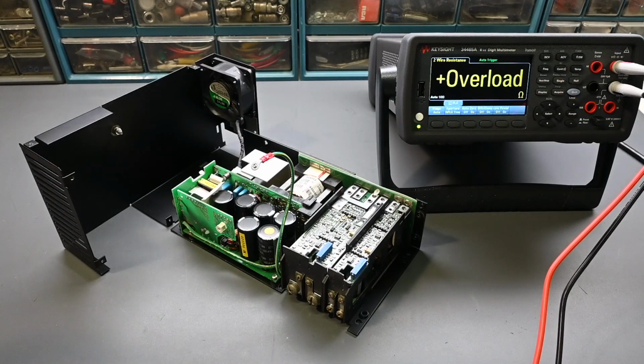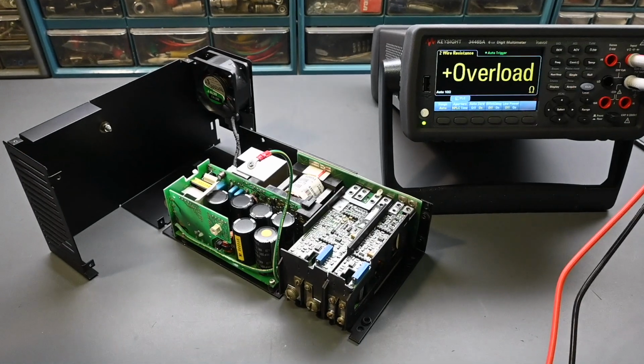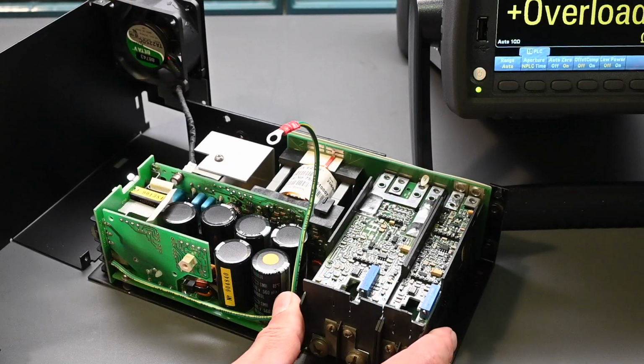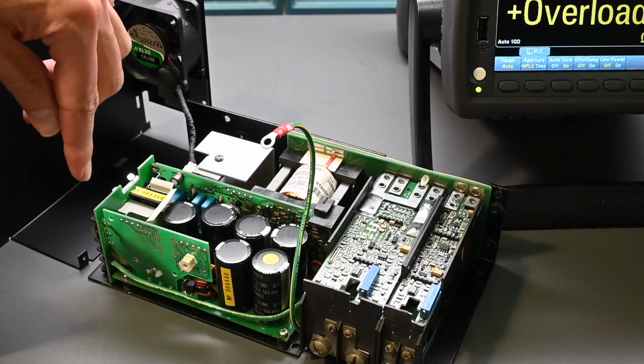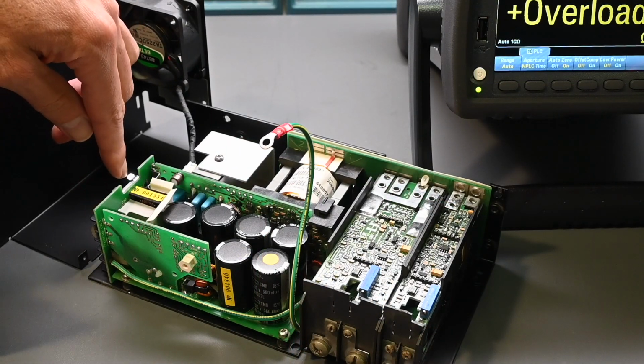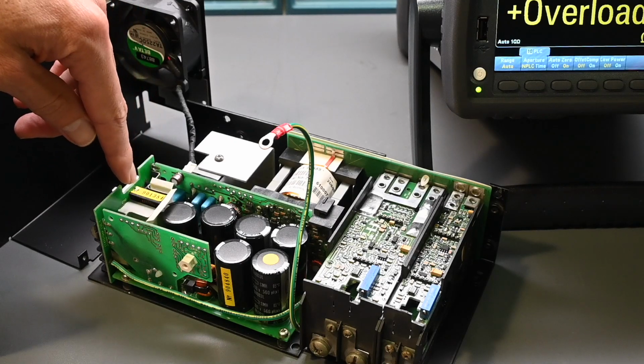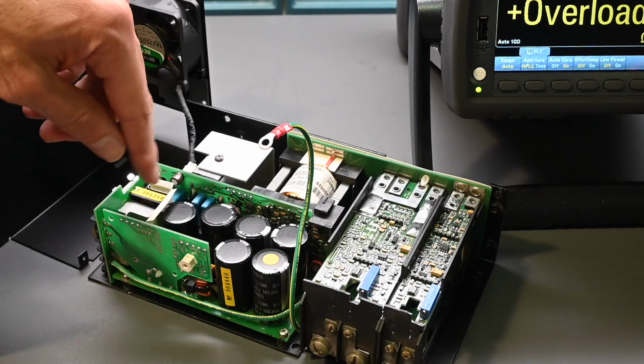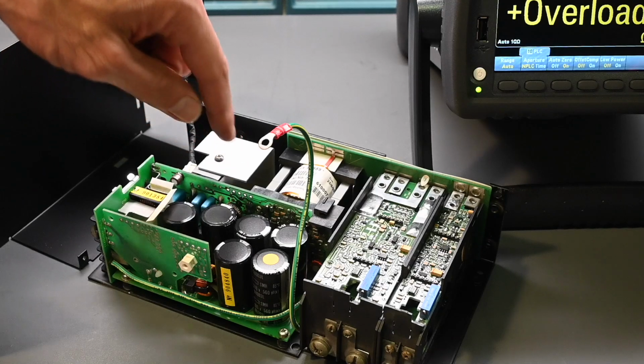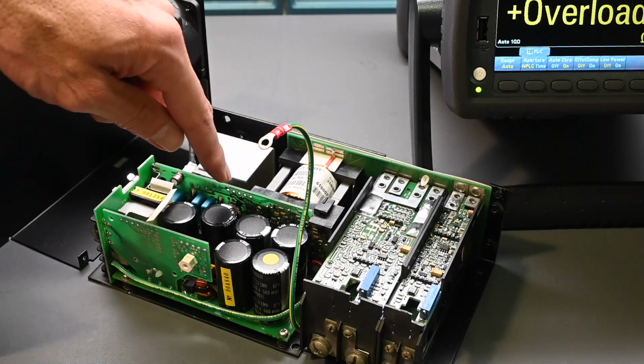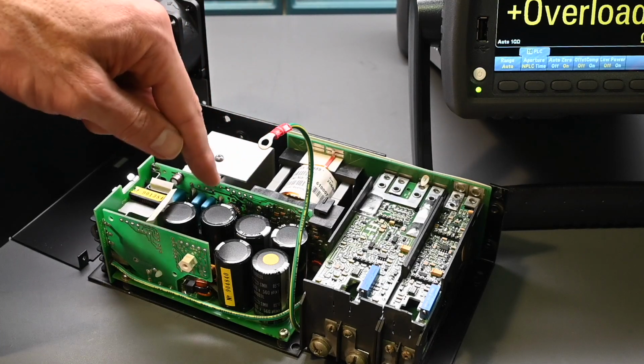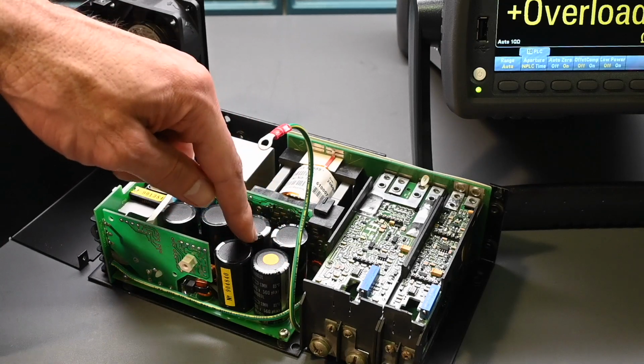So let me get you zoomed in a little closer here, so you can see the general layout inside the power supply. The AC line comes in over here on that terminal board, there's a fuse for protection, and some filtering going on over here. Then the AC line is passed into a bridge rectifier down on the bottom, on a heatsink over here, and that rectifies the AC line to DC, which is then filtered by this large bank of capacitors.